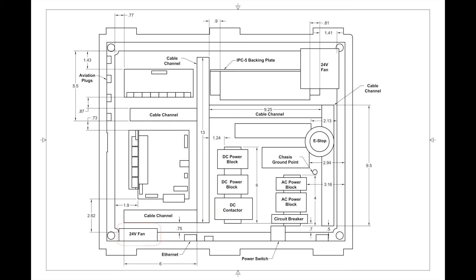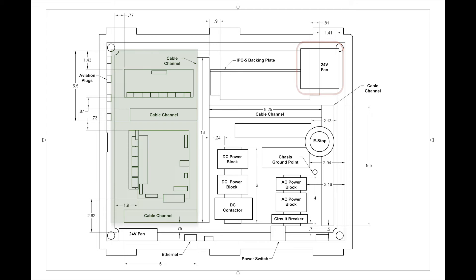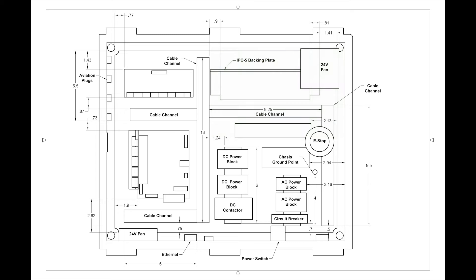I use two fans in my enclosure, one on the side for air intake and one on the cover of the enclosure in the opposite corner, to get good airflow over the controllers and then to remove the heat from the power supplies, particularly the IPC5 75V supply. The main circuit breaker and power switch are located close to the incoming main supply.